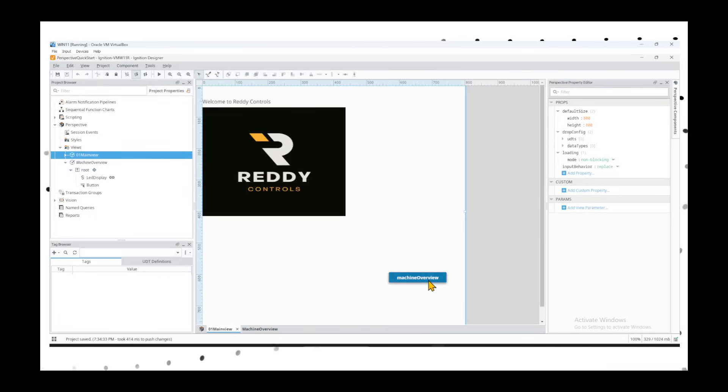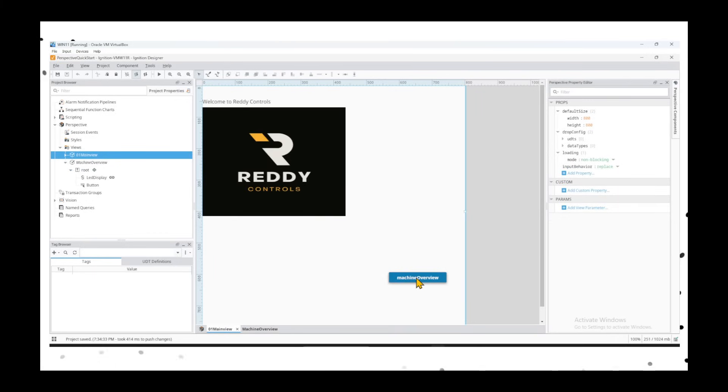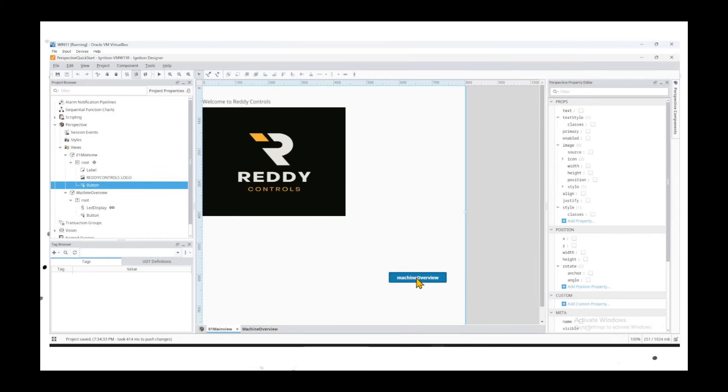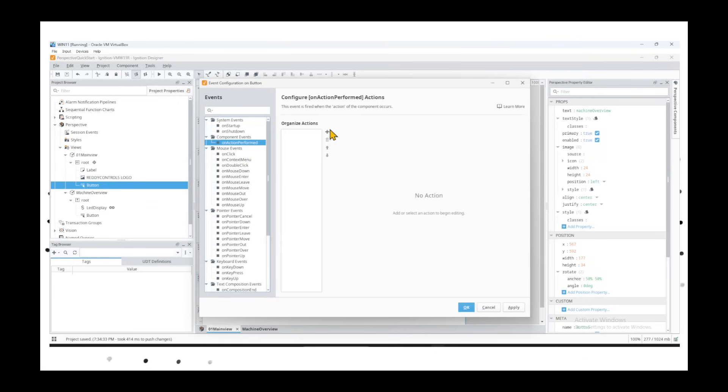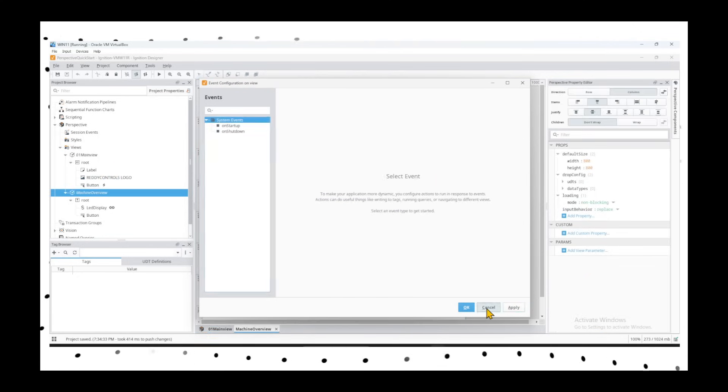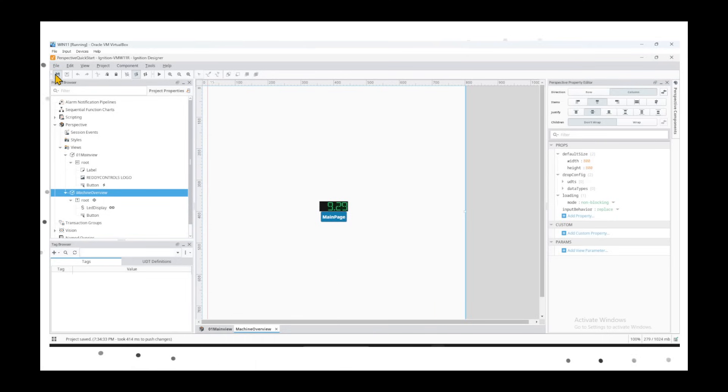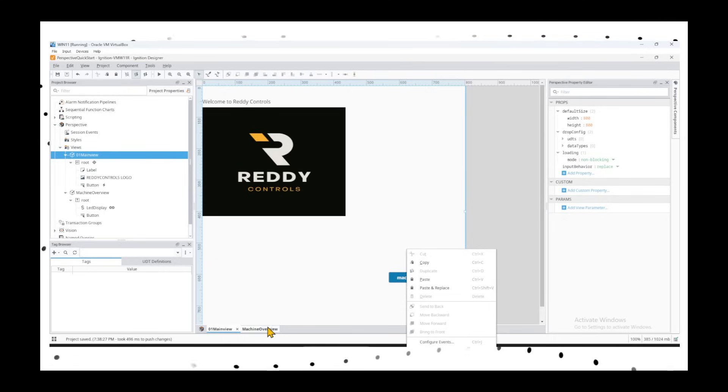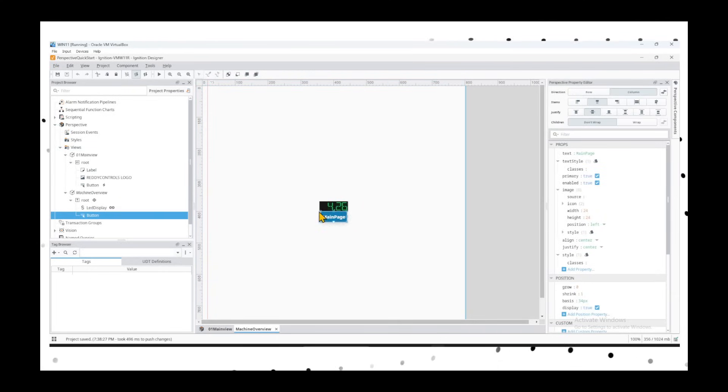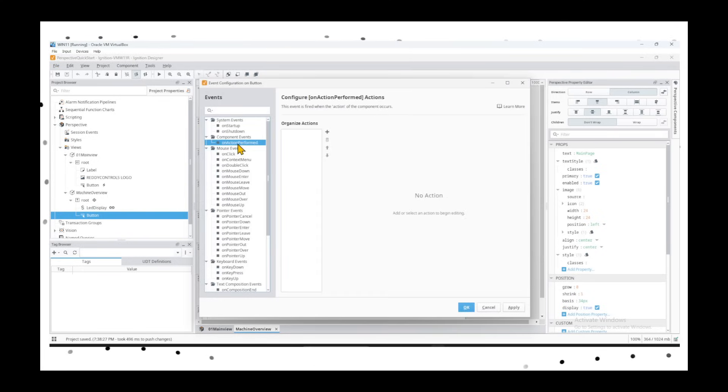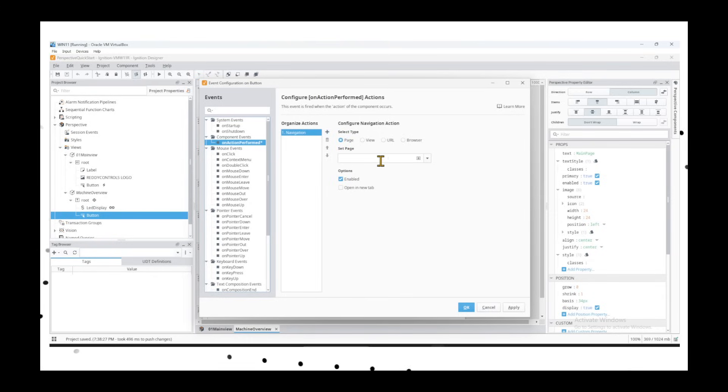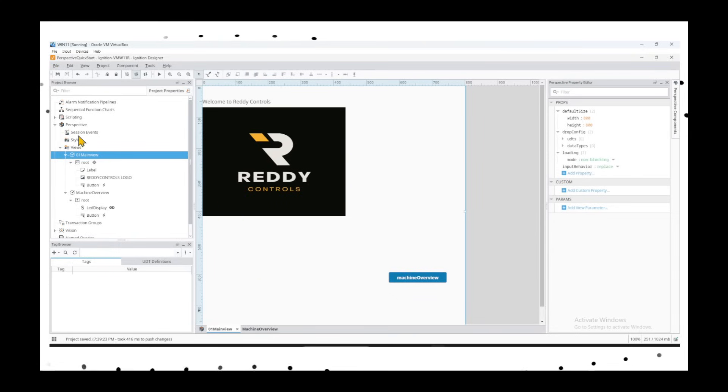Now we've created both buttons - one to go to the machine overview and on the machine overview going back to the main page. We'll configure events. Right-click, select the component until you see the dots around it. Then you'll have an option to configure events. On Action Performed, select Navigation, and choose which screen to navigate to. Apply. That's how you create navigation between perspective pages.